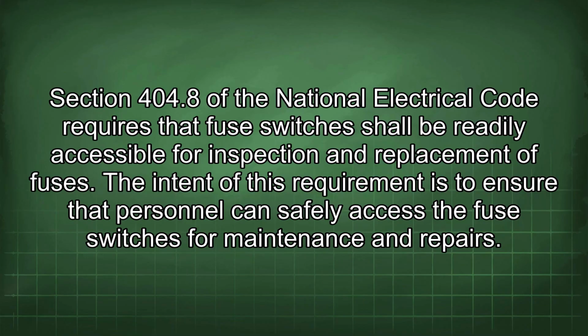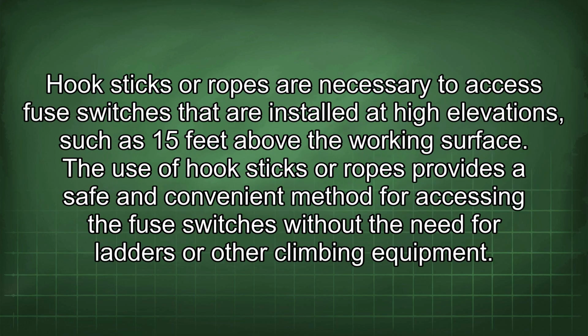Section 404.8 of the National Electrical Code requires that fuse switches shall be readily accessible for inspection and replacement of fuses. The intent of this requirement is to ensure that personnel can safely access the fuse switches for maintenance and repairs. Hook sticks or ropes are necessary to access fuse switches that are installed at high elevations, such as 15 feet above the working surface.